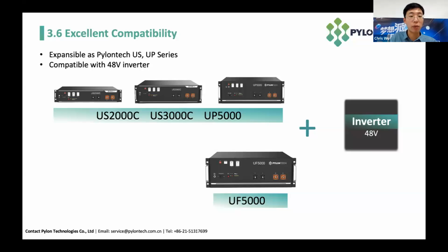For example, if a customer has a US 3000C and wants to expand his system, he can purchase a UP 5000 and use the larger one as the master battery. UF 5000 cannot be used with US 2000C, 3000C, or UP 5000, because the voltage level is different. But all of them can be used with a 48 volt inverter in the market.